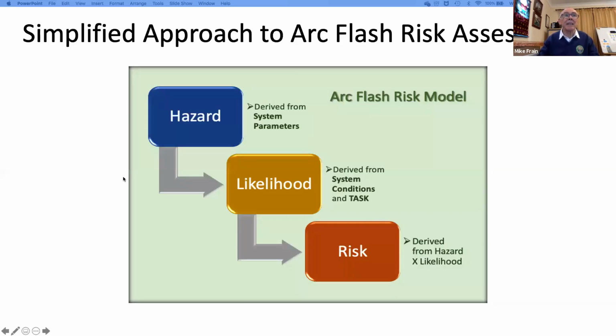This is my simplified approach to arc flash risk assessment. We've got the usual hazard, likelihood, and risk. And we know if we've got high hazard, high likelihood, there's going to be high risk. If we've got high hazard but very low likelihood, it's likely that the risk is also going to be low. Hazard, in this case, is derived from system parameters. So it's about the impedance of the network, about protective devices, and so on. The likelihood, however, is derived from what you're actually doing there in the first place. What is it? What is the task?